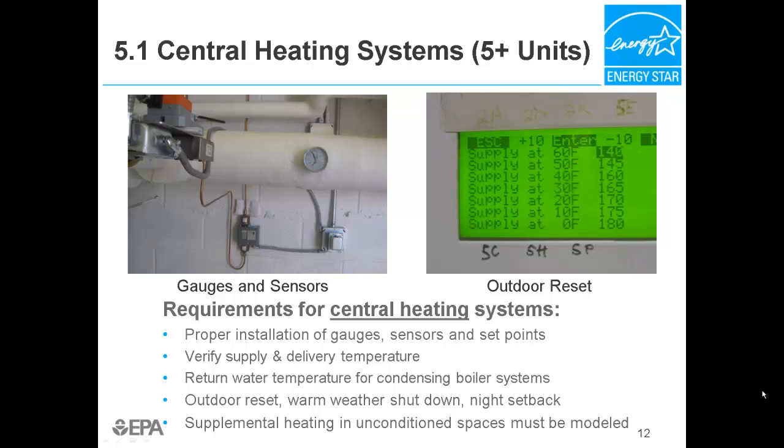Additionally, when you're in the field, be sure to verify the following. First, that temperature gauges have been installed. Take readings. Second, that the outdoor temperature sensor has been installed in the correct location and that it's functioning properly. Third, that the supply temperature is set correctly and that the sensor is functioning properly. Fourth, the location of the hydronic heating system. Is the boiler room located on the roof or in the cellar? How is combustion air venting configured? How is boiler venting configured? Fifth, that piping is insulated correctly. And sixth, that return water temperature meets design.